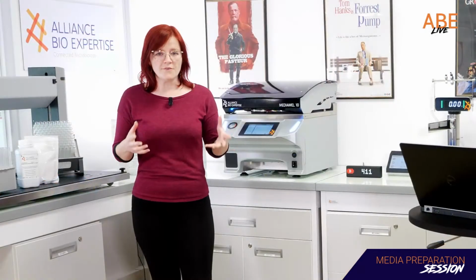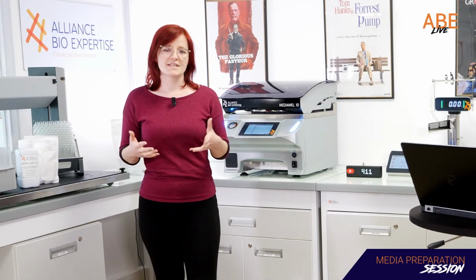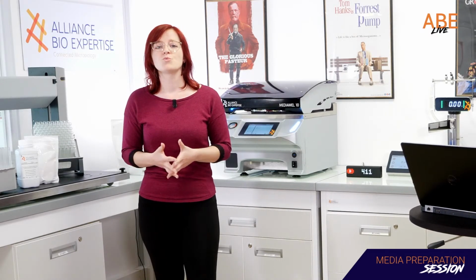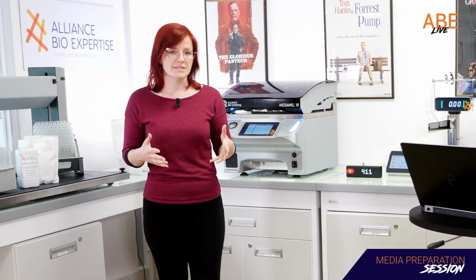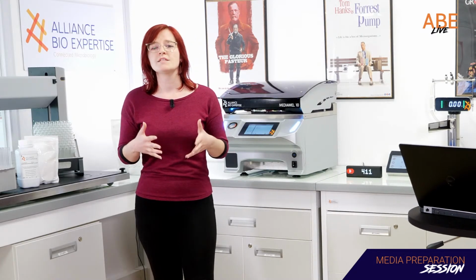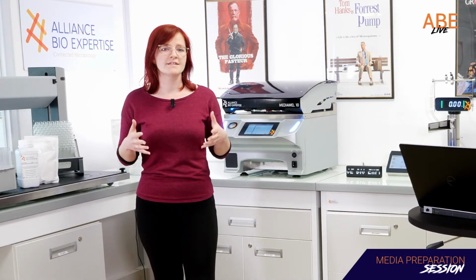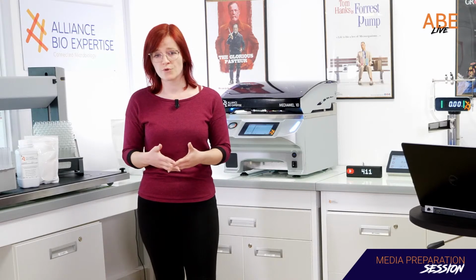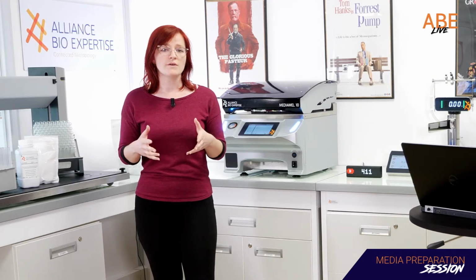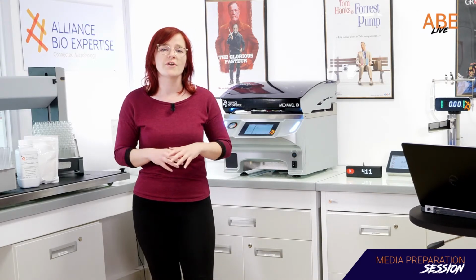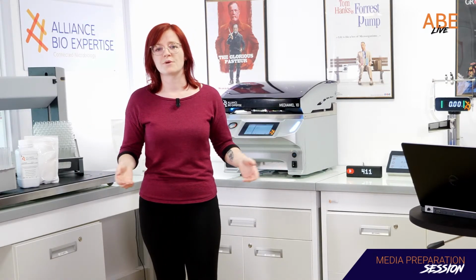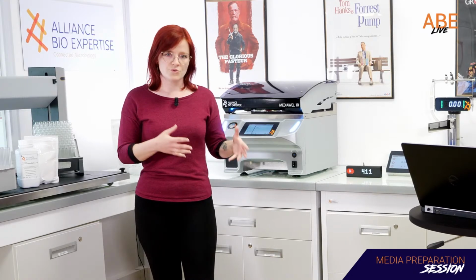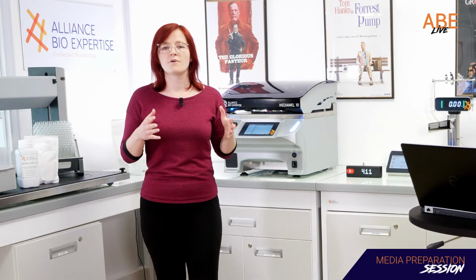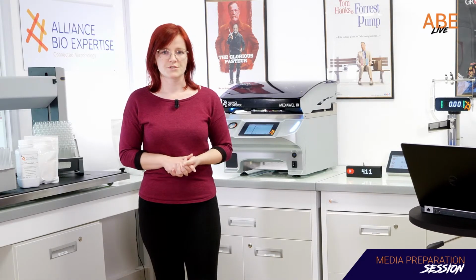Okay. And do we need other specific material when we use one or the other method once again? Well, with the manual method, of course, we've said it, you will need an autoclave, but you will also need a laboratory magnetic stirrer, and you will also need flasks, an amount of flasks that can be quite large according to the volume of media you need. Without forgetting that these flasks, you will need to clean them afterward, which is again enlarging the time the media preparation will take. When you go with the media prep, you will only have one vessel, only the media preparator.